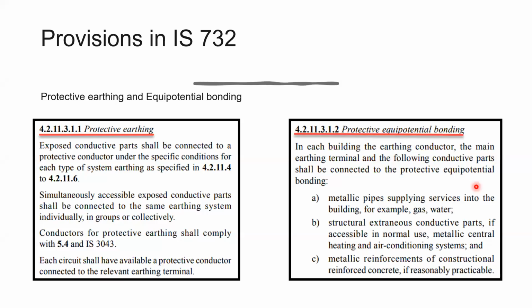And IS 3043 also gives a reference to clause 5.4 here, which talks about the unearthed systems. In case of the unearthed systems, some means of detecting the ground fault should be installed, and in case of the earthed systems, the ground fault is indicated by the automatic interruption. So both the 732 as well as the 3043 talk about the automatic disconnection of the power supply in case of fault.